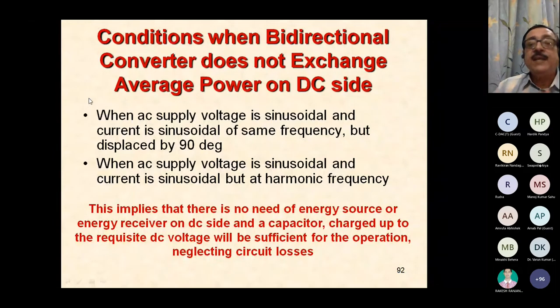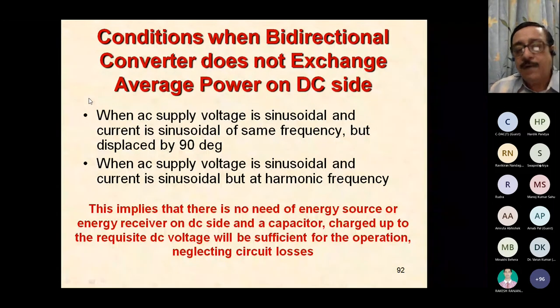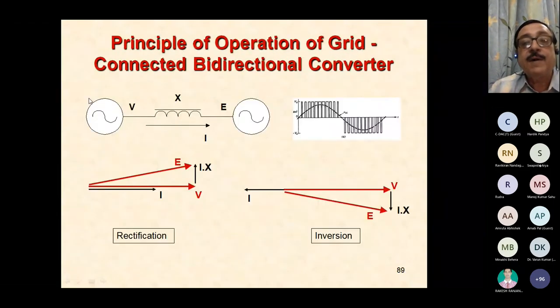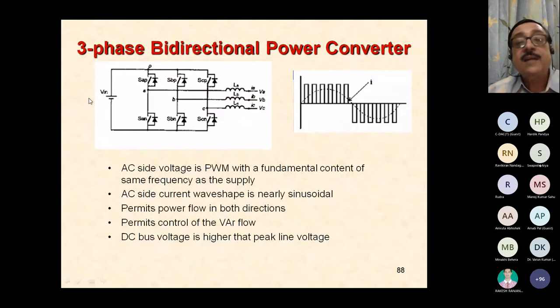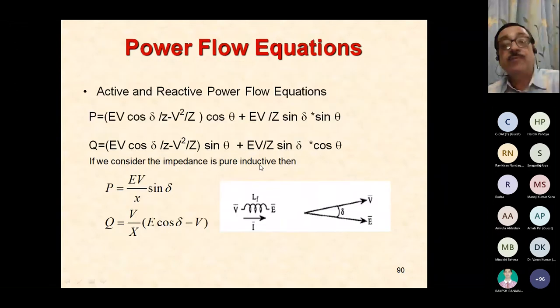That is when the voltage and currents are of same frequency but displaced by 90 degrees. With a 90 degree displacement, you know that no active power can be transferred. Then why do we do it? We can send reactive power. The whole converter will behave as a source of reactive power now. Suppose this converter is connected to the grid. This can handle reactive power, and it is up to you to make the converter with the current lagging or leading so that it depends what type of VAR you are trying to compensate. That is your control totally.